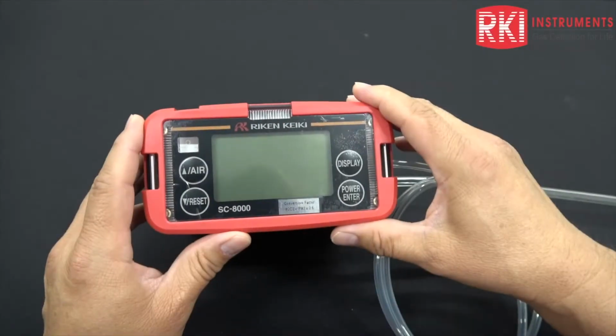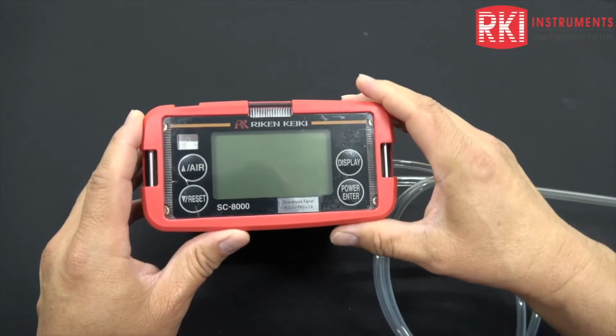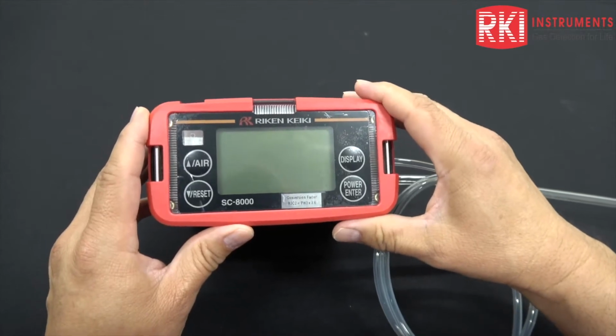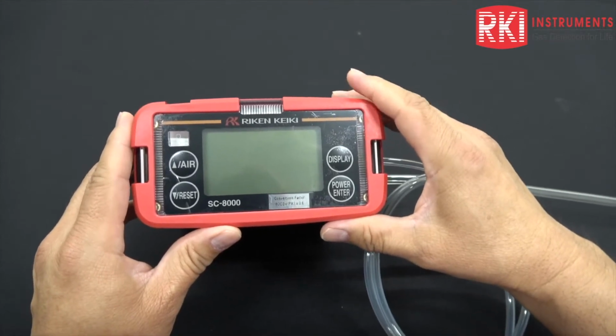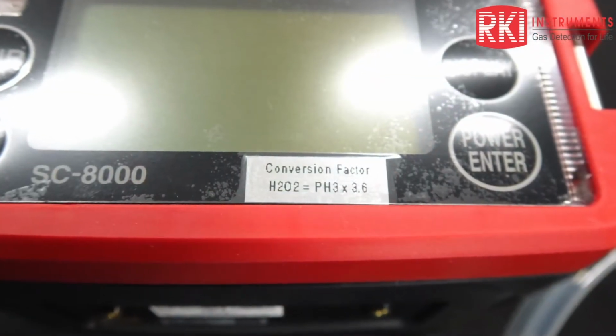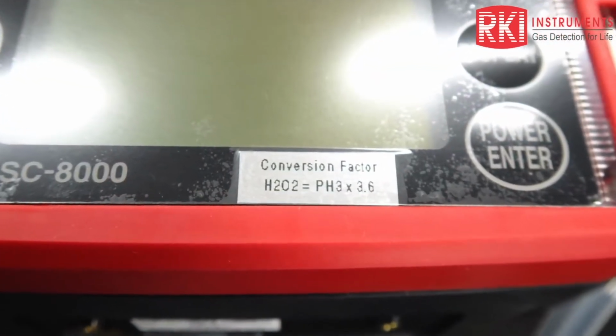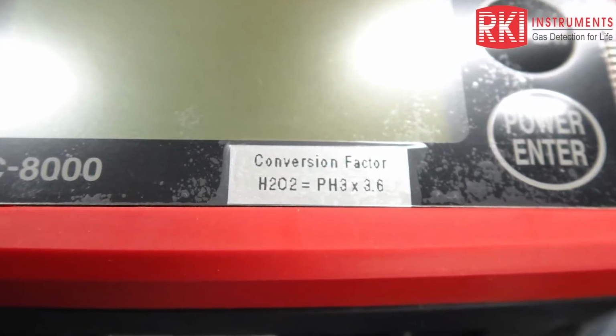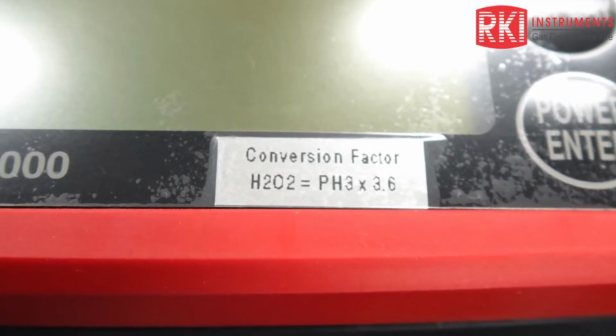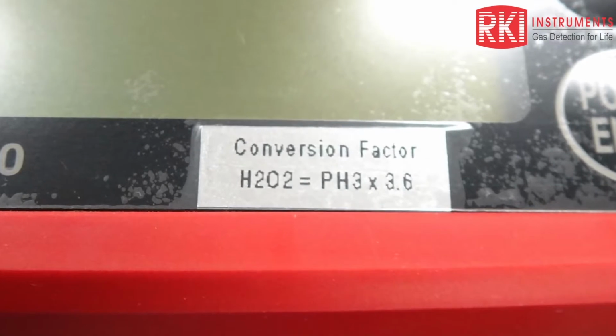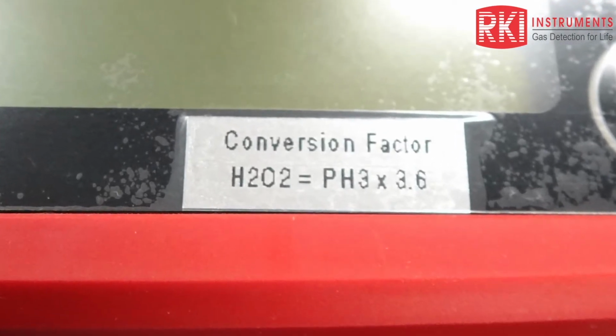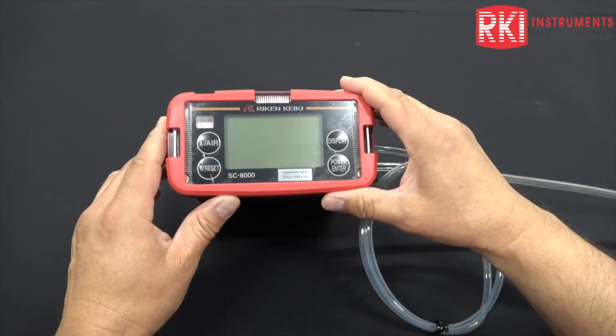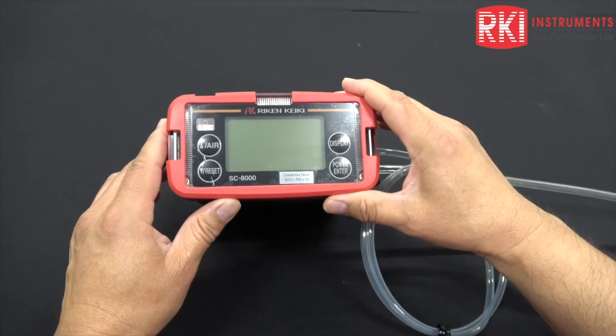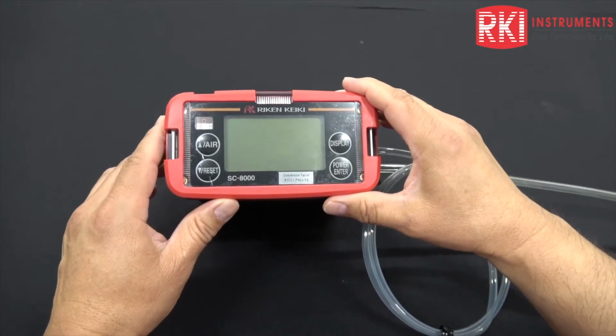Today I want to show you how to calibrate our model SC-8000 portable gas monitor. This monitor is measuring for hydrogen peroxide, which has the formula H2O2 on this little label here, which gives a conversion factor of phosphine, which is the calibration gas we use as a surrogate calibration gas, times 3.6 equals H2O2. So we're going to be diluting a phosphine sample down low enough so it can be read by this unit.